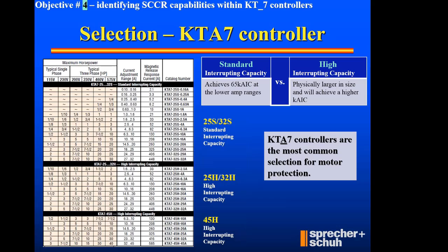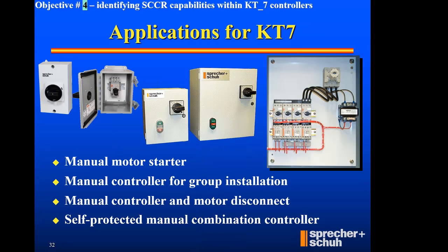What's standard interrupting versus high interrupting? When we look at the SCCR ratings on the next screen or 2 or 3, you'll find that KTA7 typically will allow you a 65 KAIC offering, and that'll be predominantly in the lower ranges. So you'll see 65 in the lower, but as you increment into the higher ranges, the KAIC value goes down and then it eliminates after a while. So that would be the reason to move up to the next size product or a higher interrupting rating kind of product. That's the difference between standard and high: in the lower amps we can get by, but if you're not achieving the interrupt capacity required, you're going to have to move to a higher interrupting. So that was the offering page.